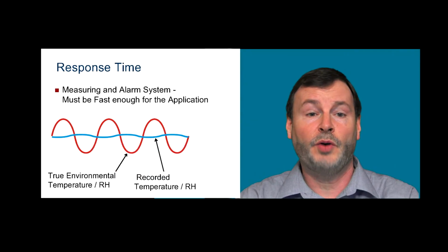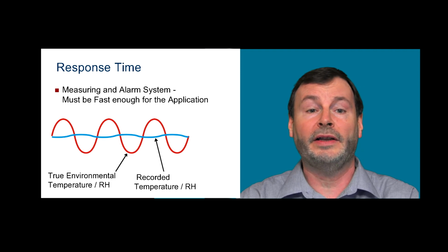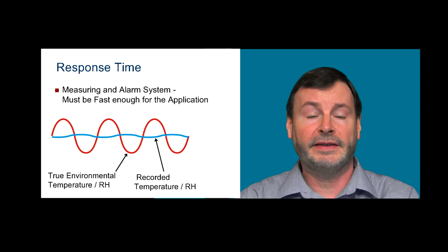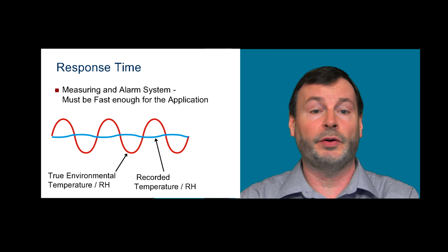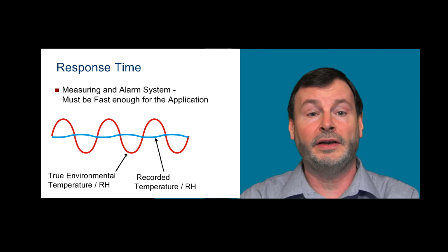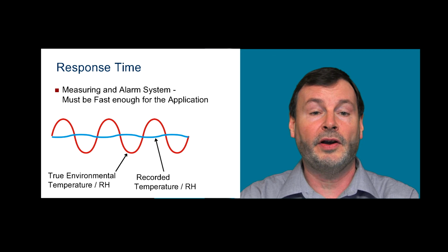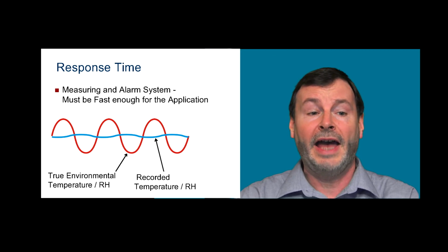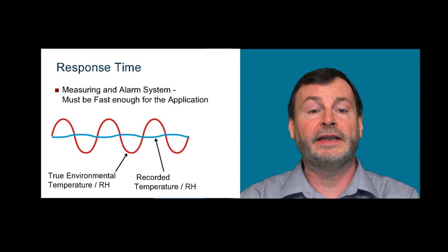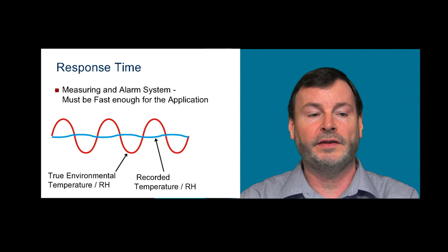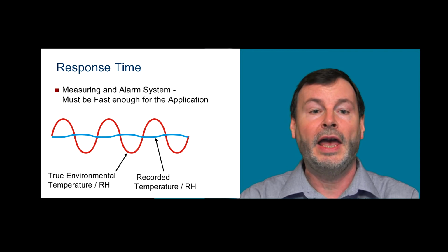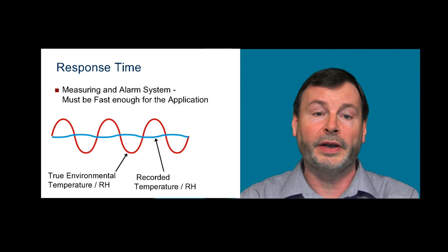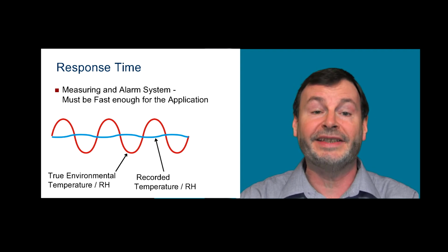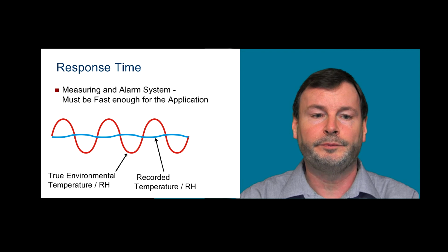Now, some materials and products don't really respond that quickly, and this may be fine. But in some cases, if those excursions are extreme, like getting to very high humidity or very low humidity, depending on the application, we may want to have a better idea, both recording and sometimes even more importantly, is that we get fast alarming to know things that are going on. So again, it depends upon the needs of an application, and it's important that we select a monitoring and alarm system that's appropriate in speed for the application.